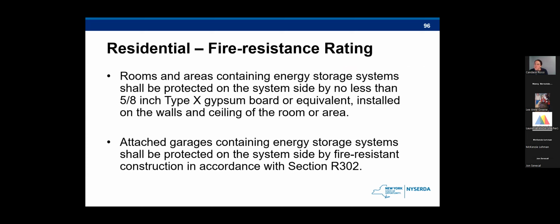There is a specific fire resistance rating that must be met. Rooms that contain energy storage systems have to be protected by a fire resistance rating of 5/8 inch Type X gypsum board or equivalent installed on walls and ceilings. Attached garages have to be protected on the system side by fire resistant construction, which I believe for R302 is basically a 1 hour tested, 1 hour resistance from exposures on both sides. Basically, this ensures that if there is an incident, the walls can resist spreading the fire, and you'll have enough time to evacuate.